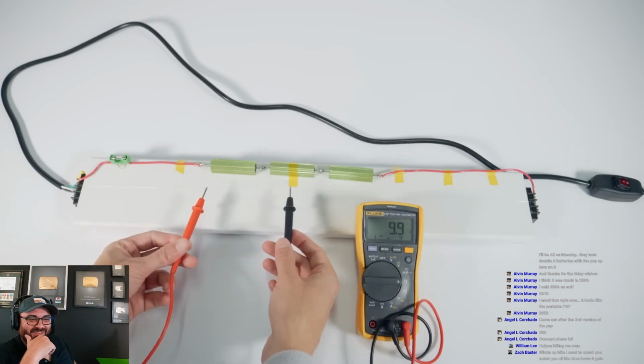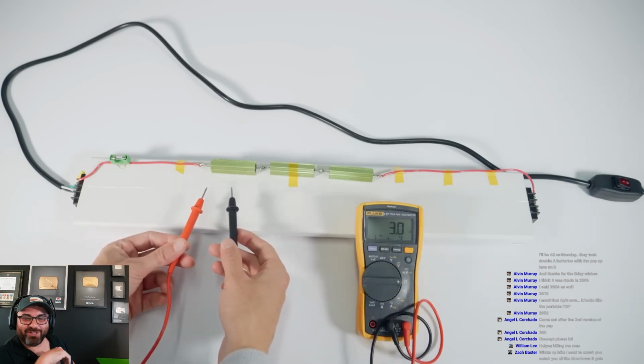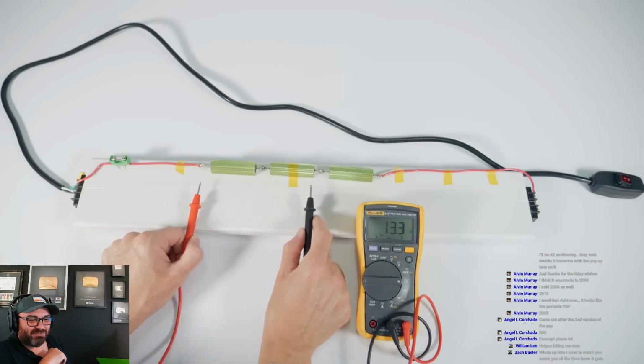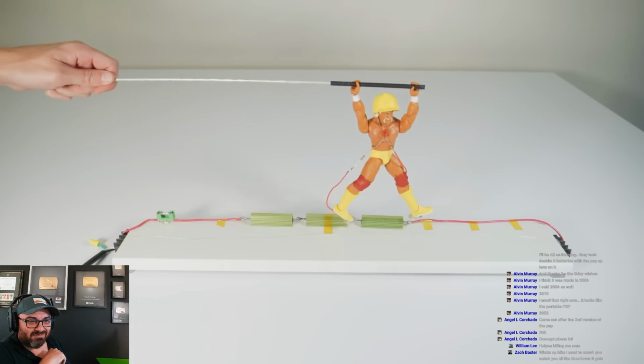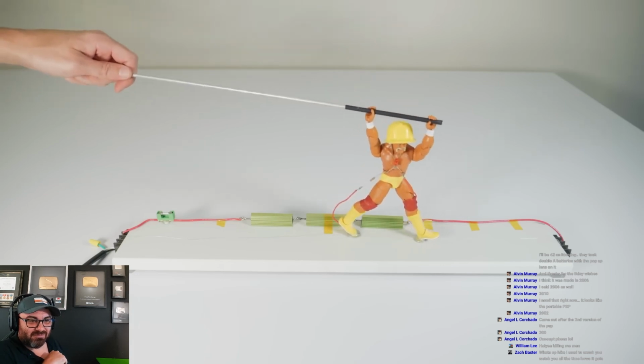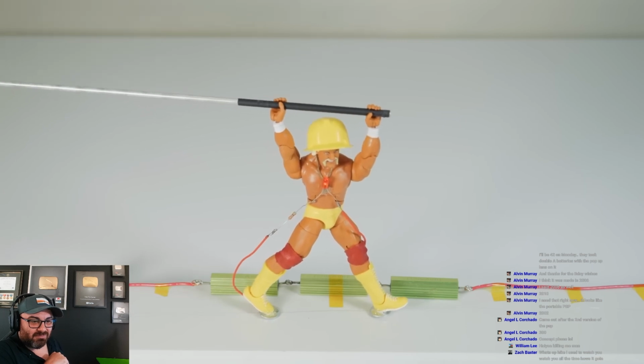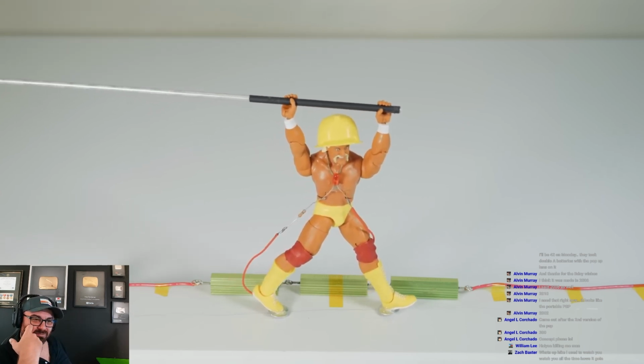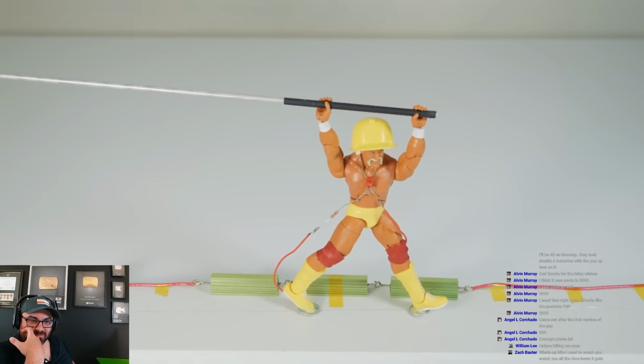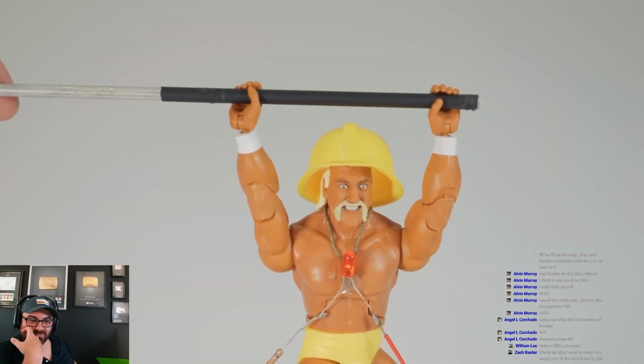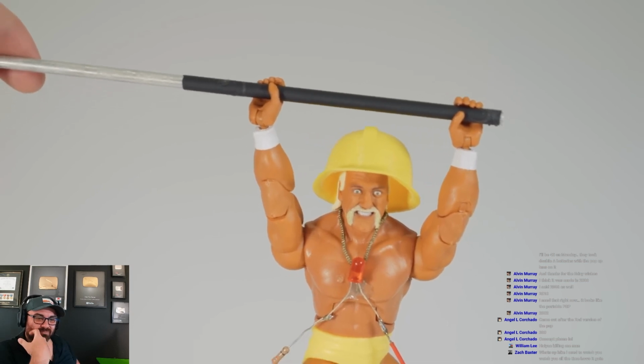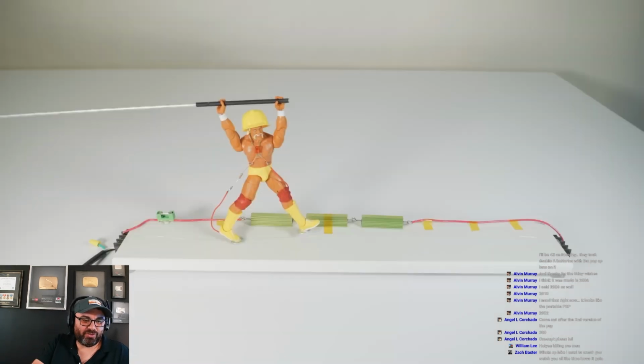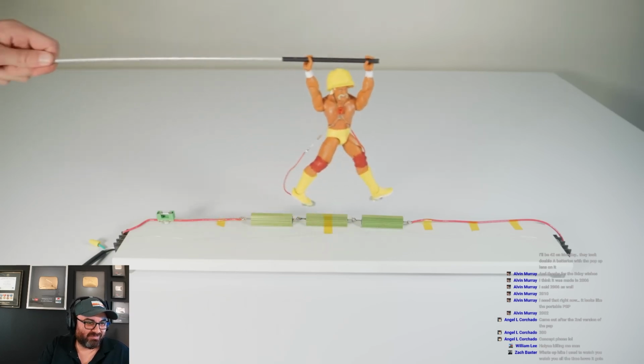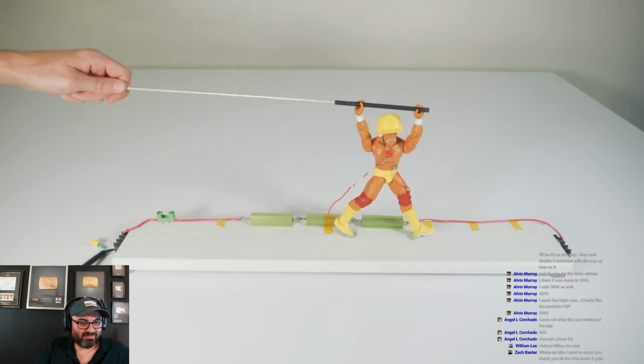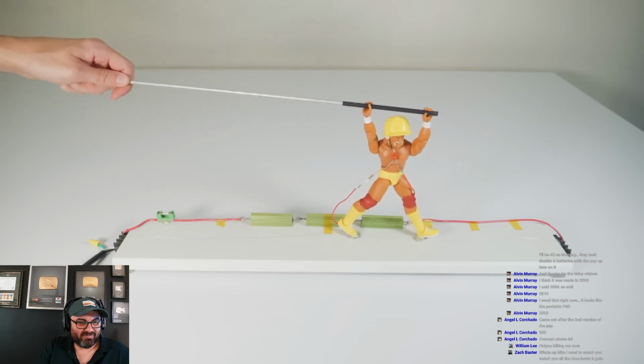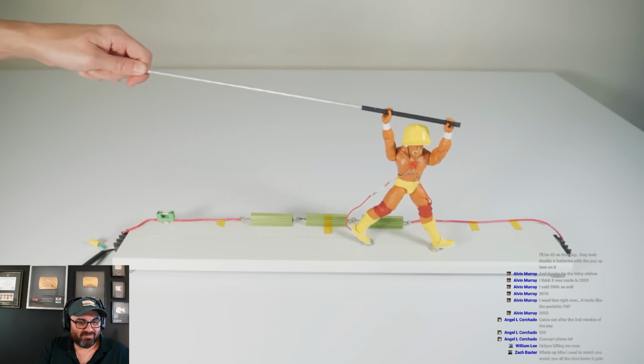I can show that just by measuring the voltage with a meter at a few different locations. Remember that voltage is the difference in potential between 2 points, or in the case of Zap McBodyslam here, between 2 feet. When Zap steps on the wire, his legs are at 2 different electric potentials, and unfortunately, human bodies are better conductors than the ground. That difference in electric potential creates a voltage that drives current up into one leg and down out of the other. In this case, I just have that voltage turning on a little light, but depending on how high that voltage is and how well Zap is insulated from it, this step potential could be a matter of life or death.